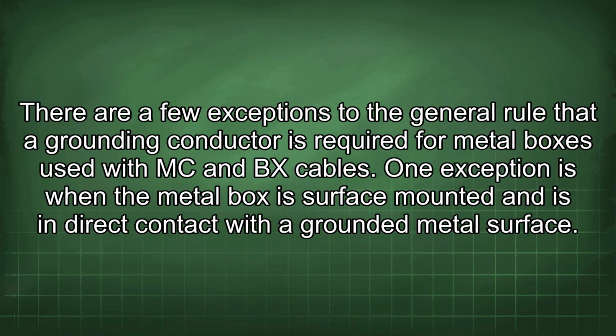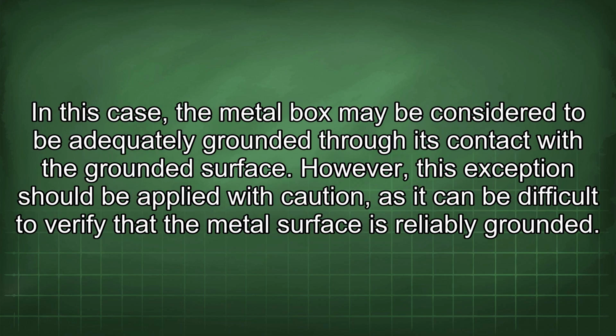There are a few exceptions to the general rule that a grounding conductor is required for metal boxes used with MC and BX cables. One exception is when the metal box is surface mounted and is in direct contact with the grounded metal surface. In this case, the metal box may be considered to be adequately grounded through its contact with the grounded surface. However, this exception should be applied with caution, as it can be difficult to verify that the metal surface is reliably grounded.